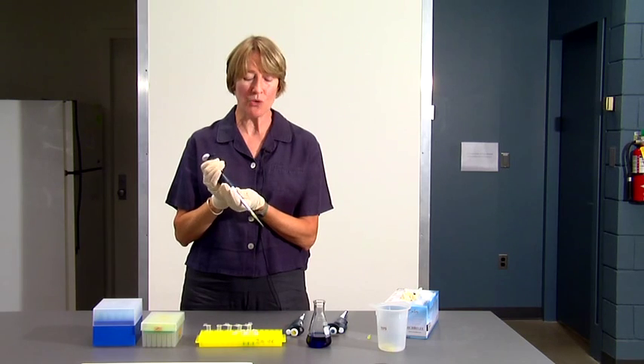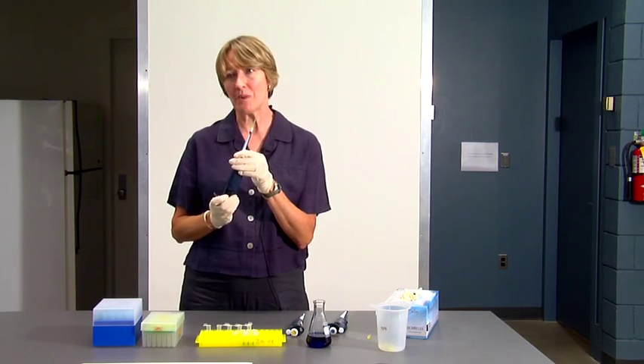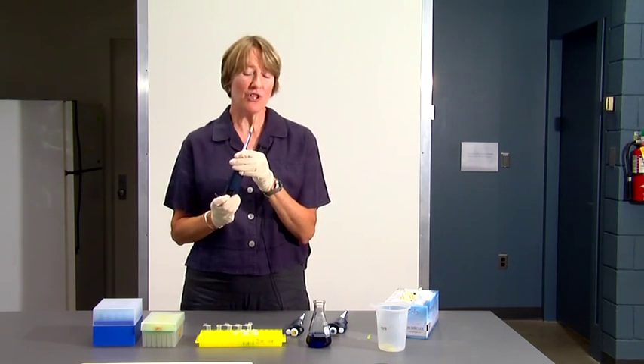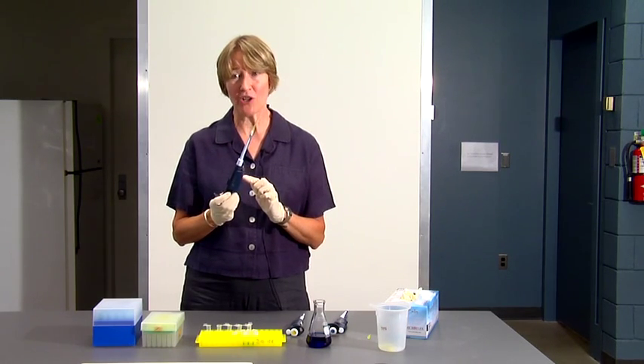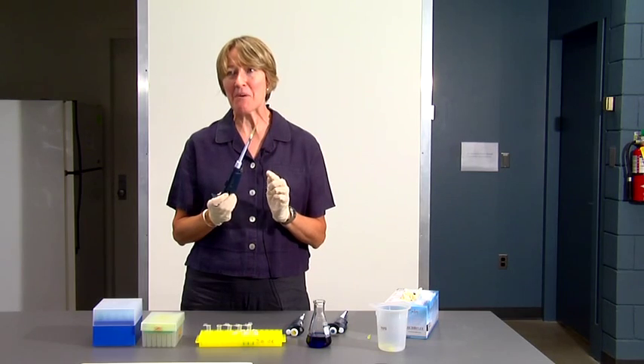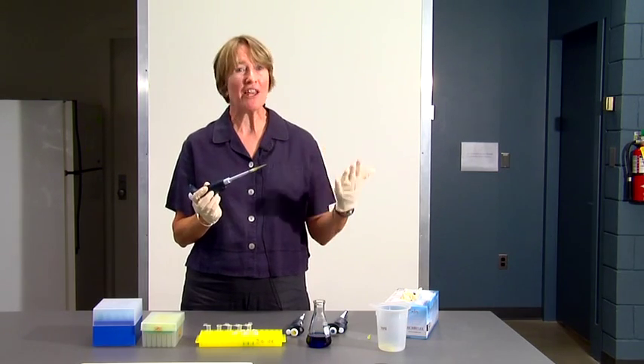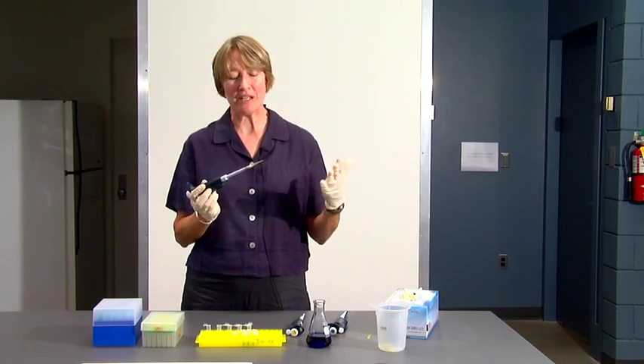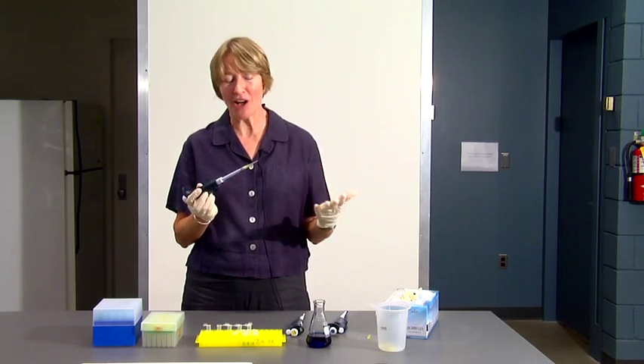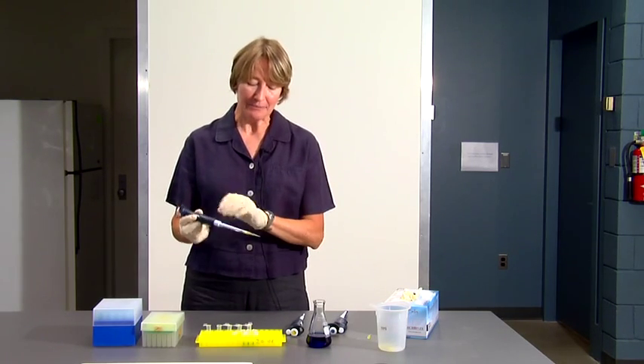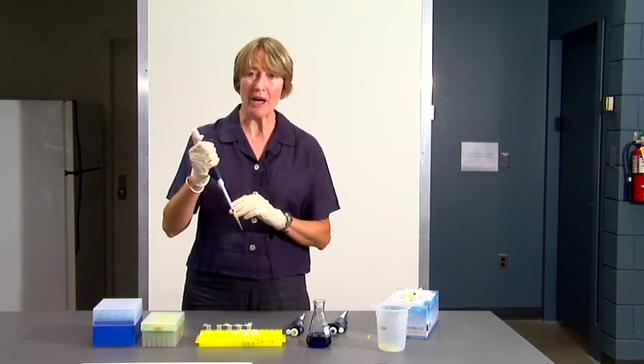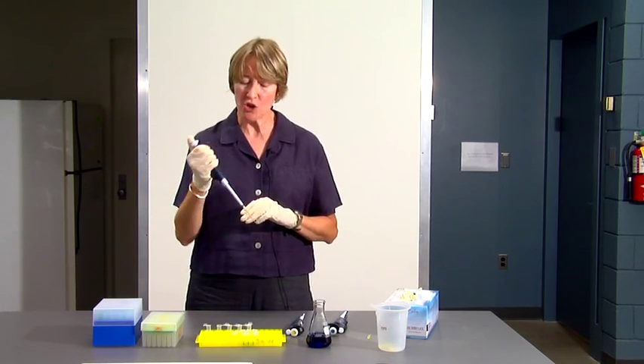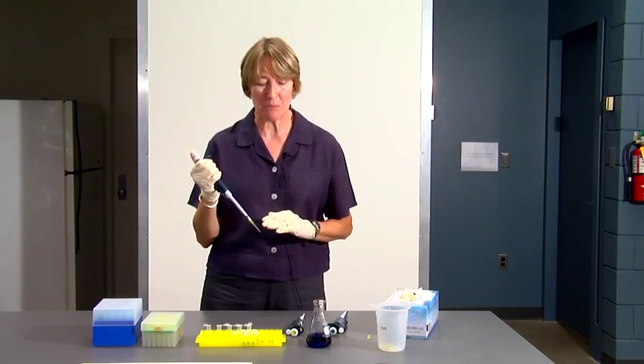Another thing you should never do is turn your pipette tip up like this. If you do that, the fluid in the tip will flow down into the pipetter. It will contaminate the pipette. And if you're using radioactivity or bacteriologicals, that means we now have to take the pipette apart, clean it out, and start over and recalibrate it. So always hold your pipette tip in this position or at an angle with the tip down.